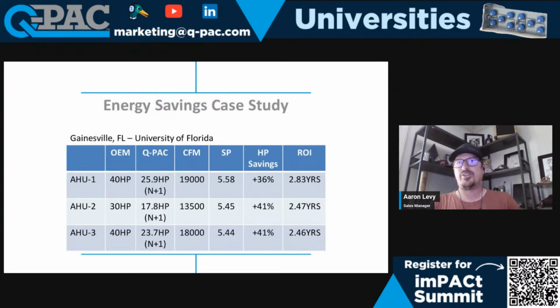This is an application we did at University of Florida. They had a 40, a 30, and a 40 horsepower system there. When we did the retrofits for those solutions, we were able to save them anywhere in the 40% energy cost range. We weren't just giving them like-for-like - we gave them an N+1 solution, adding an extra fan as a safety buffer, which still allowed them to keep it under 3 years of energy payback. That's kind of where they'd fall on average. This example is at 5.5 inches of static, which is a little on the high side, but 2.5 to 5.5 inches of static pressure range is kind of the bread and butter for these systems.